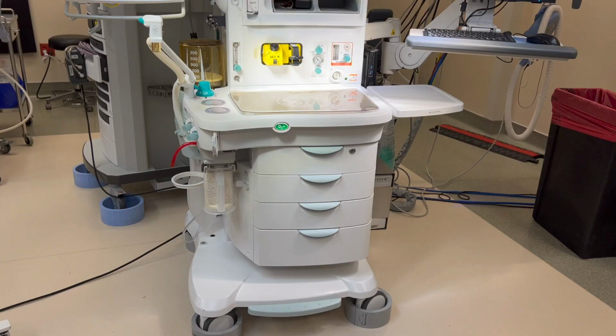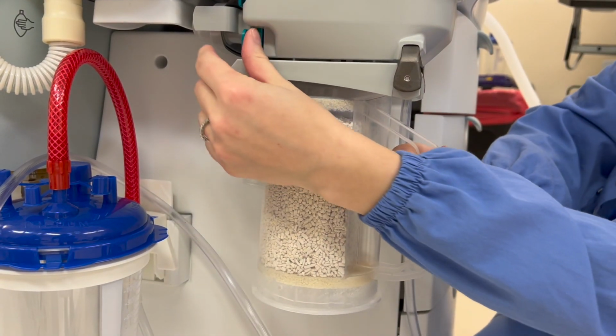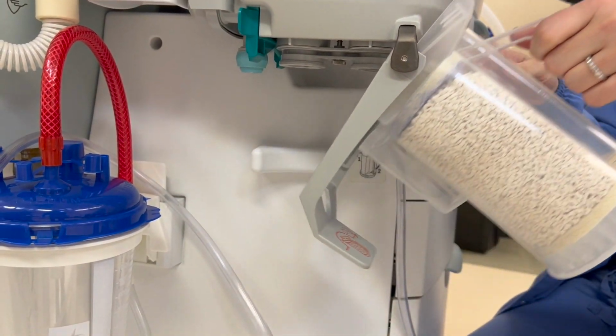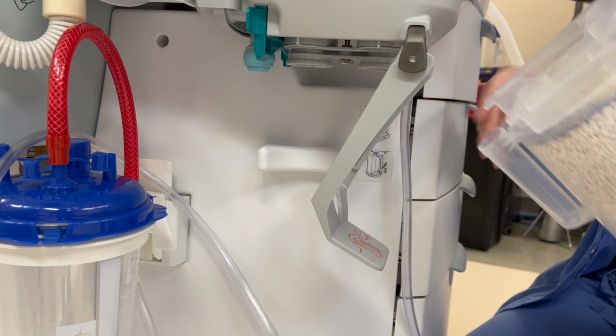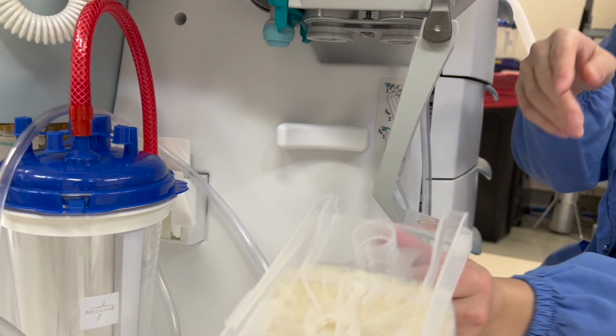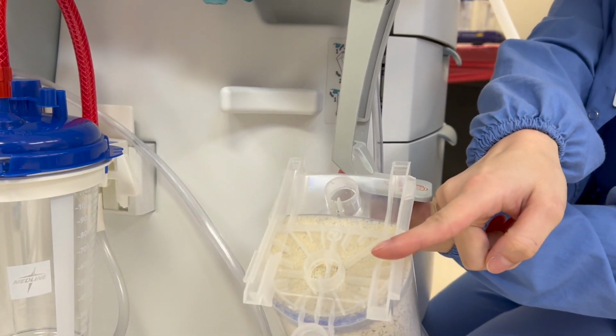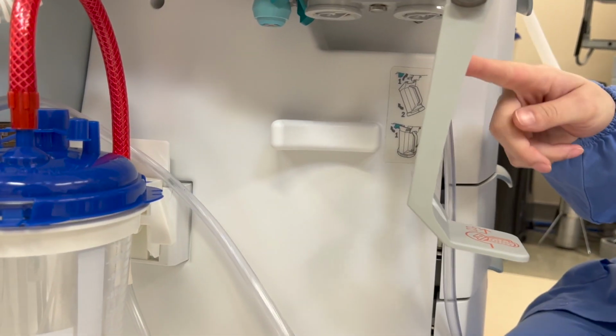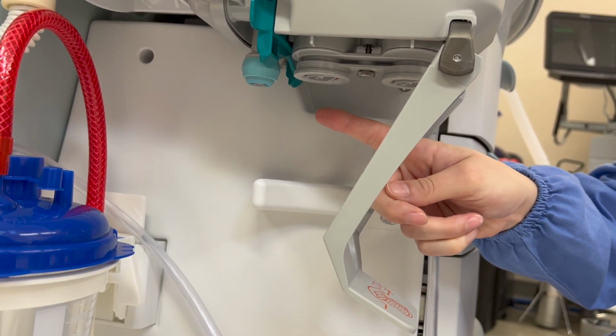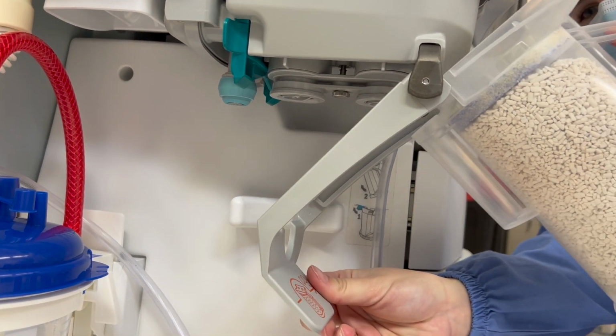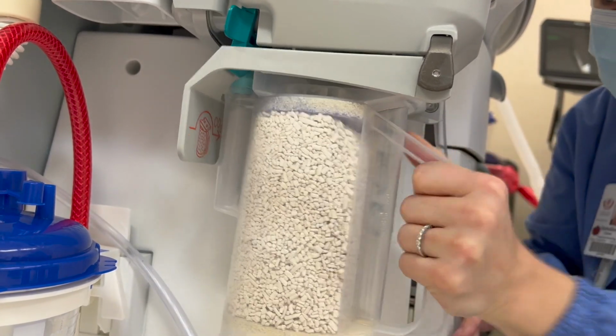The CO2 absorber is on the lower left of the front of the machine right here. You can release it by pressing this green latch forward, and then you can slide out the CO2 absorber. This latch is not the same as the latch we used earlier for the flow sensors and O2 sensor, so be careful that you don't confuse the two. When you take out the CO2 absorber, you're going to notice that there's 2 holes at the top. Those 2 holes have to match with the 2 holes that are coming down from the machine.